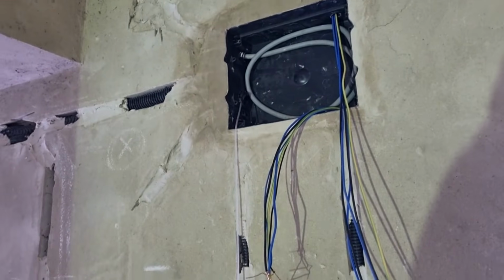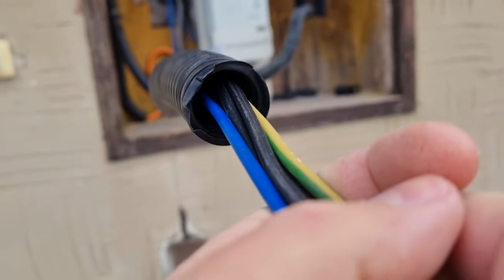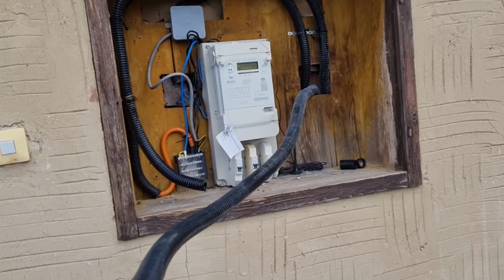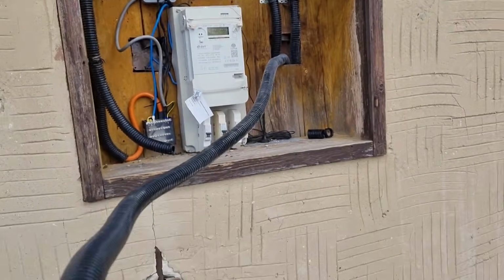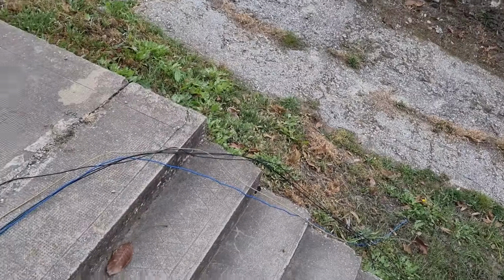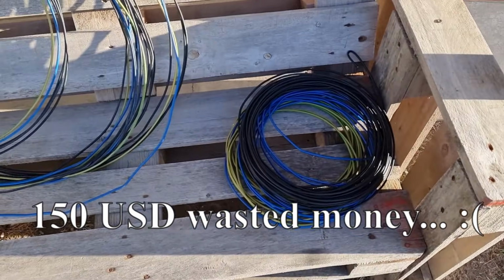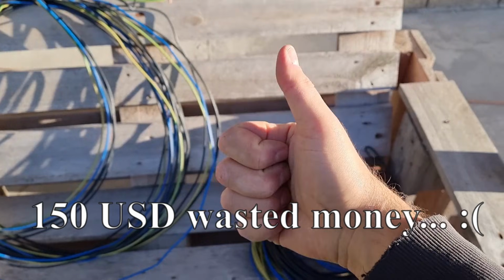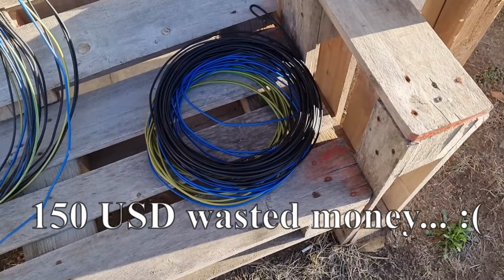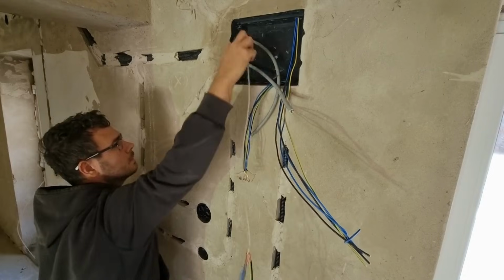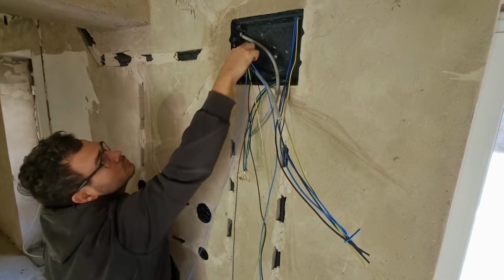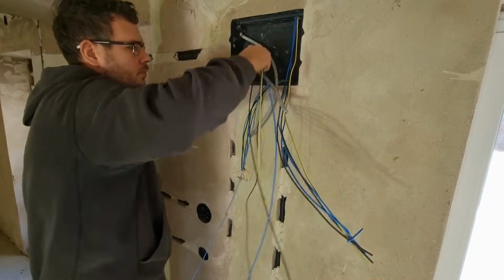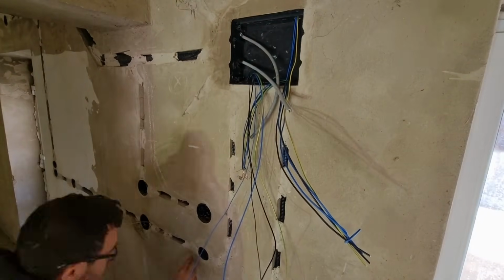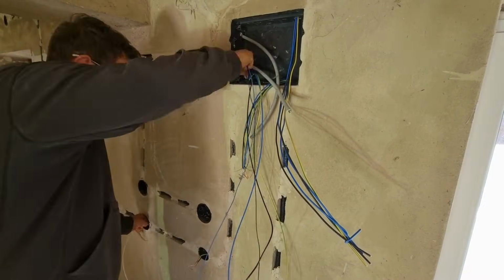Not a good combination. The main supply wire I originally wanted was 6 square millimeter. I wanted to pull it into a 32 millimeter conduit, and that's exactly why I installed such a thick conduit in advance, so everything would fit comfortably. Well, that didn't happen. After a total of 2 days of suffering and trying, I gave up on the idea that I would ever be able to pull 5 by 6 square millimeter wires into a 32 millimeter conduit. So I spent more than $150 on wire that I couldn't even use.